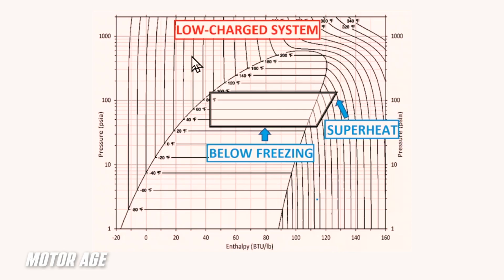Now we're going to start introducing different faults. And the significance is we're going to be able to see the faults on the chart as it's plotted against the bell curve to help us make some diagnostic decisions without having to remove refrigerant as an experiment or add refrigerant as an experiment. So in this example of a low charge system, first and foremost, the system is performing as it should. In other words, the refrigerant is doing its job. But since we are low on capacity, even though the temperature of the refrigerant entering the evaporator is below freezing, there's such a small amount of it, it can't absorb the heat out of the cabin efficiently.